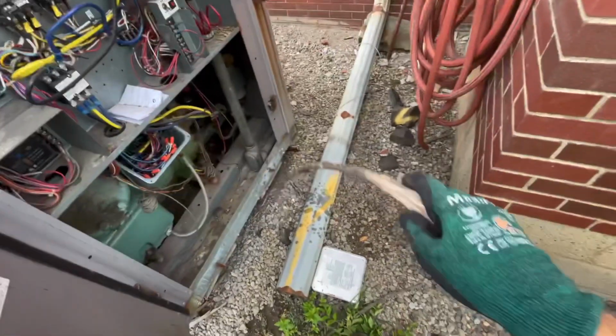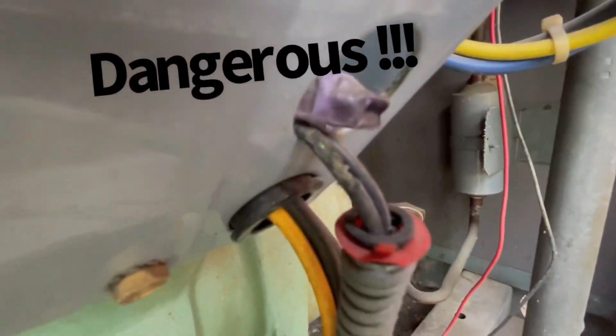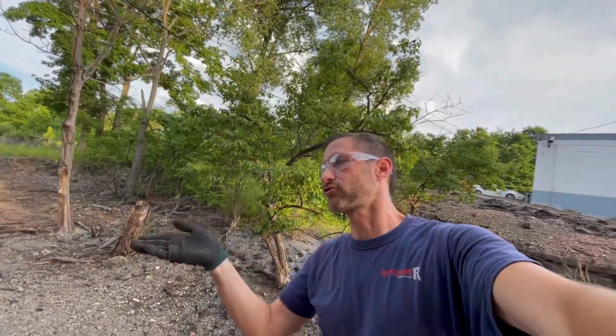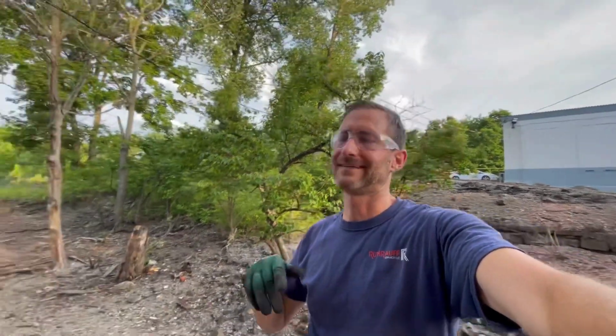Okay, guys, after I used that high-tech stick I picked up at the local supply house, I got that out of there, and if you could see, bare wire. It's going to short to ground. That's what happened. Let me get away from this yellow jacket. Get away. Go. Anyways, that was the path of least resistance, the mouse shorting to ground. It didn't trip the three-phase breaker for some reason, but it probably caused a little interference with the circuit board. Hopefully, crossing my fingers, just shut down power, tape up that wire, turn it back online, and it should fire up. So hopefully, a simple fix. Never know what to expect in this field, people. Never know.